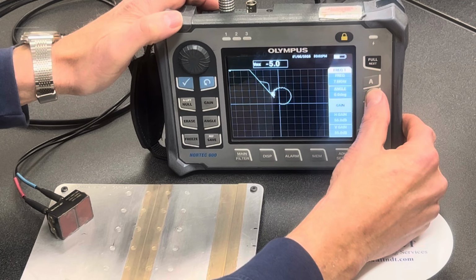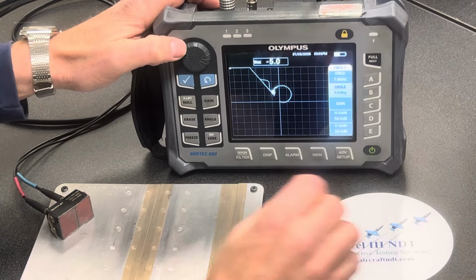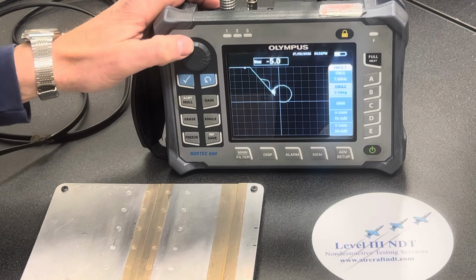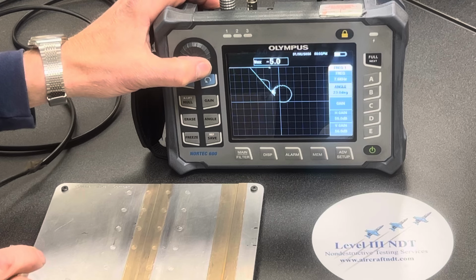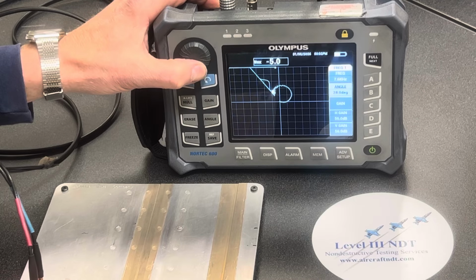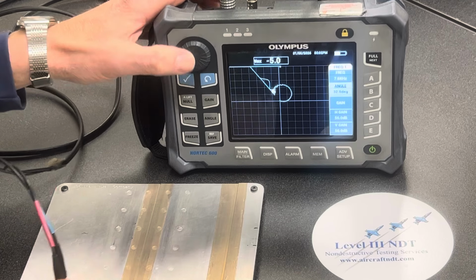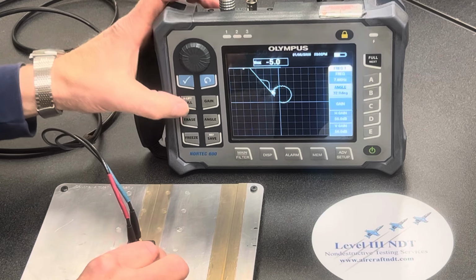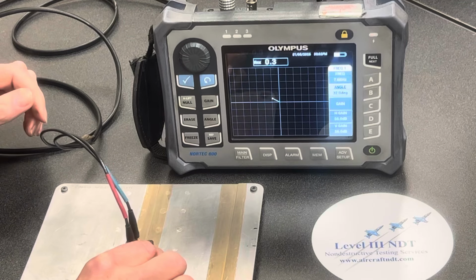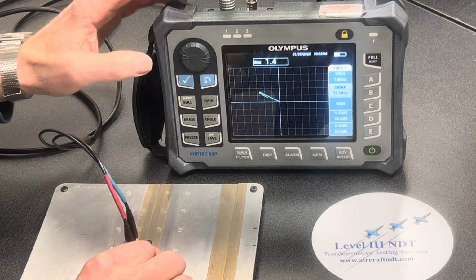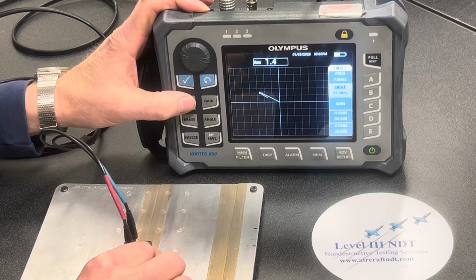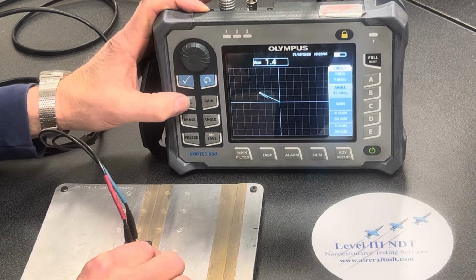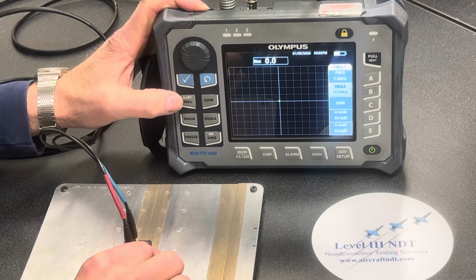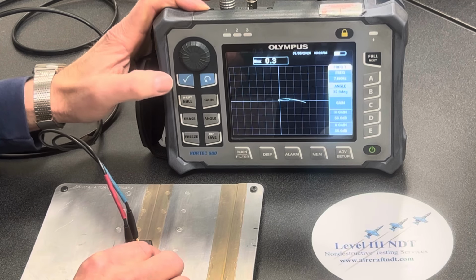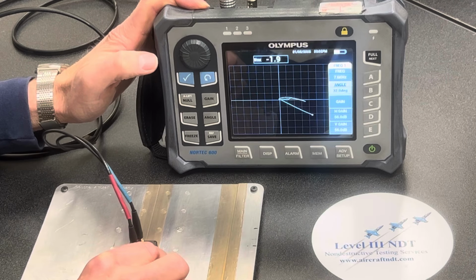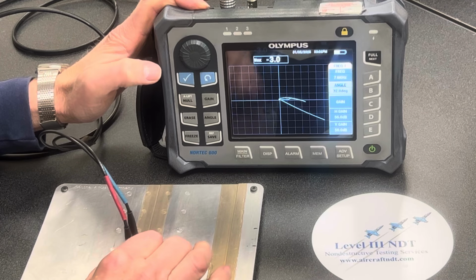And the last thing to do is set the rotation angle so that liftoff goes to the right and misalignment with the skin seam goes down and to the right. We need to null the instrument with the probe and align it on the skin seam to get the maximum signal. That tells us that we're perfectly aligned with the seam itself. So we null it there. We check our liftoff, it goes to the right. We check our misalignment and it goes down and to the right. So our phase is set properly.